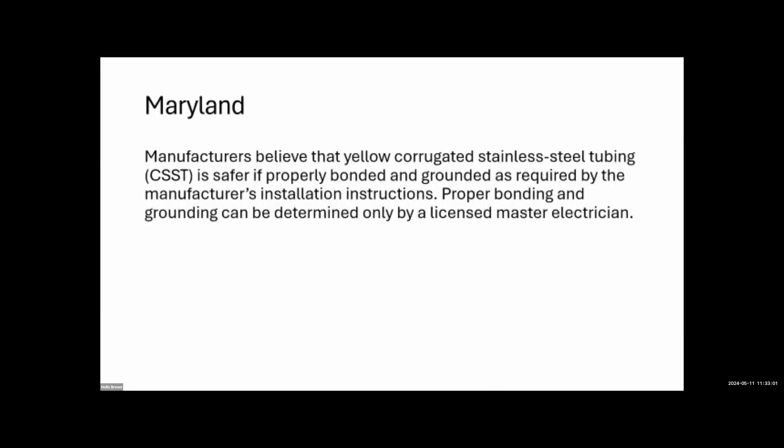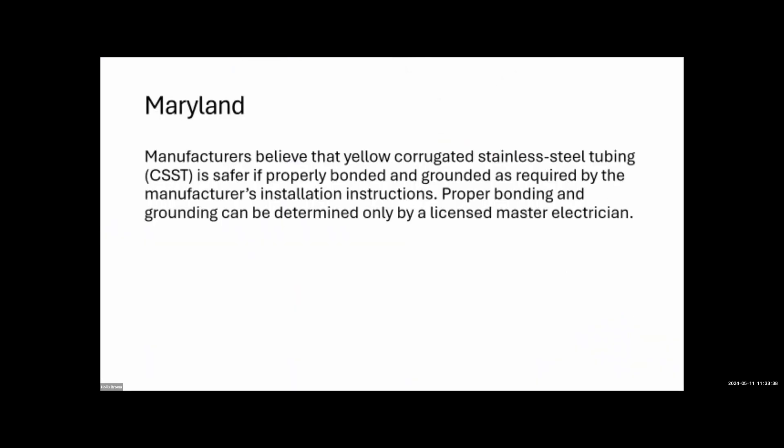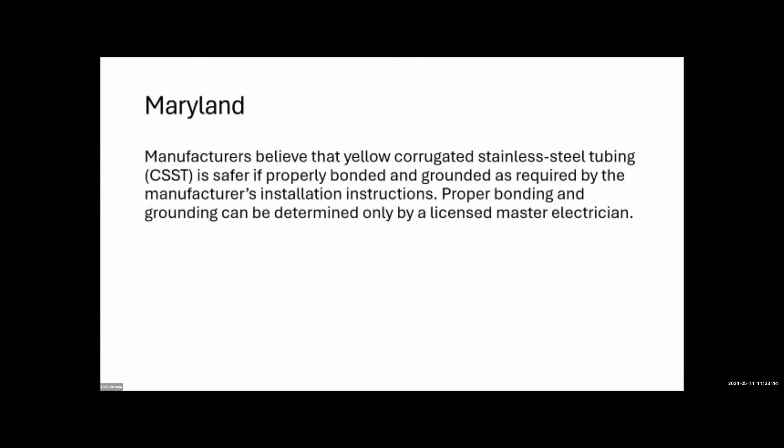In Maryland and Virginia there are specific CSST requirements that inspectors must report. In Maryland, for yellow CSST we're required to recommend that only an electrician can identify if it's properly bonded. The reason it's often not bonded is that the plumber installs the pipe and the electrician installs the bonding wire, but nobody tells the electrician to come back and bond it.